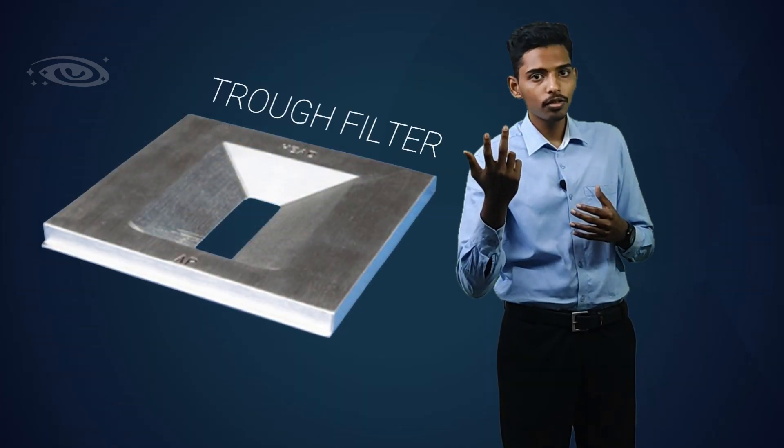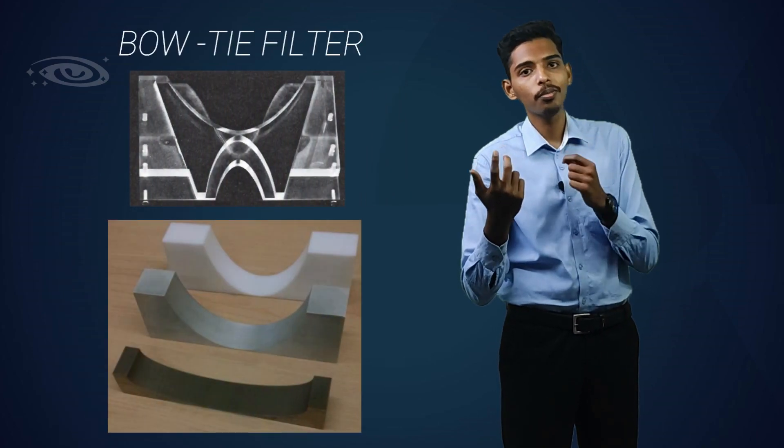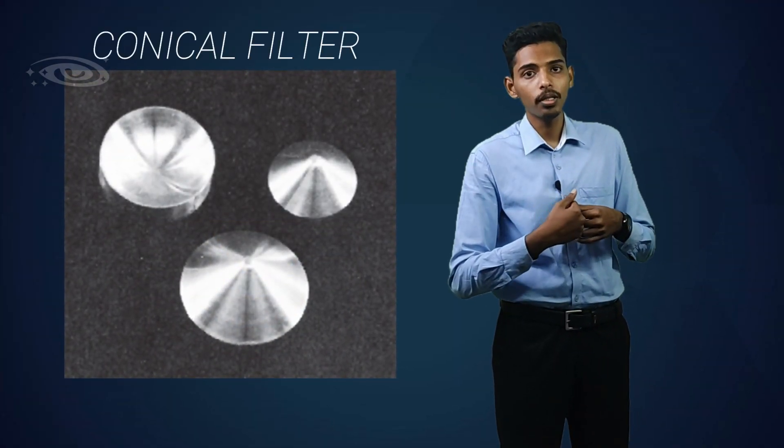We have many types of compensating filters. Some important ones are: the wedge filter, the trough filter, and the bow-tie filter. The bow type filter is the most important filter in the CT scanner. And then we have conical shape filters, which are used in fluoroscopy.